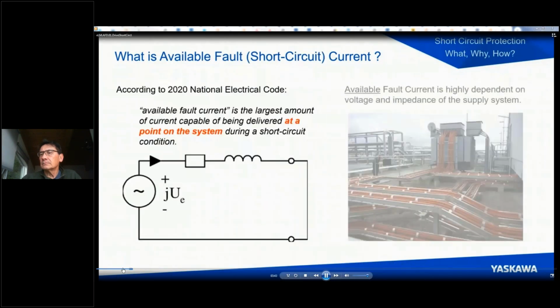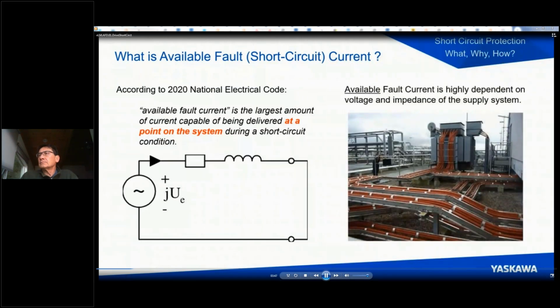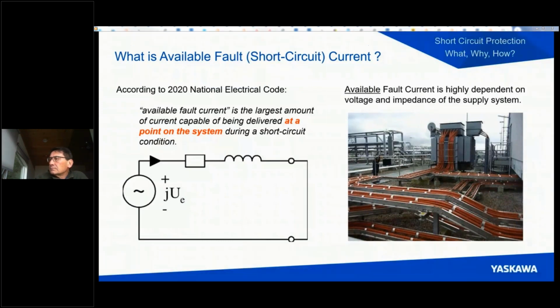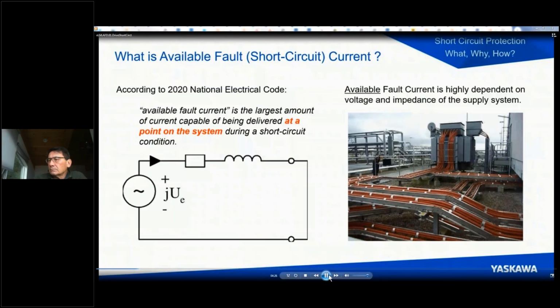So let's remember that a system generally would consist of a transformer somewhere, possibly going from medium voltage to low voltage, and obviously the available short circuit or fault current right at the terminal of the transformers will often be very, very large. But at points further down the distribution system, the available fault current at a point to which you would connect a load, such as a drive, can be a lot different than the available fault current directly at the source. So let's all remember that available fault current.